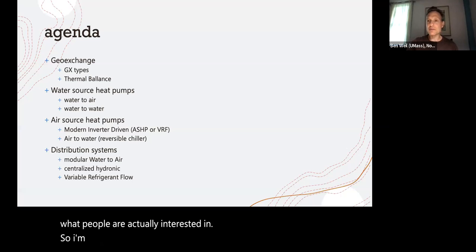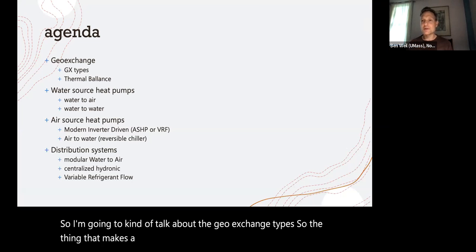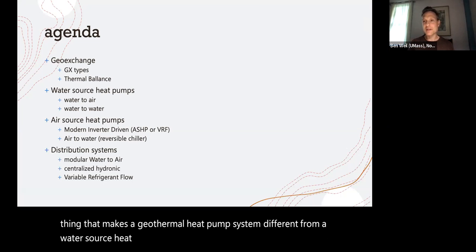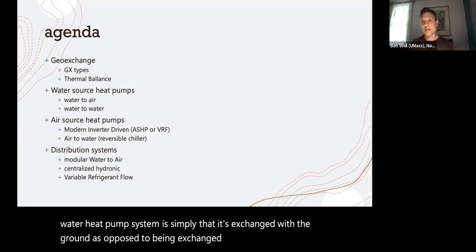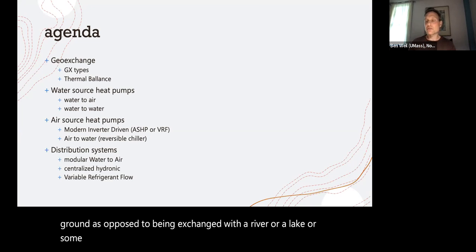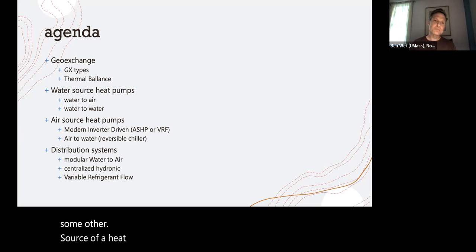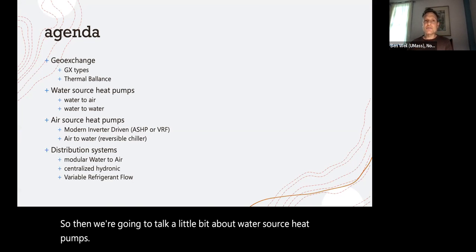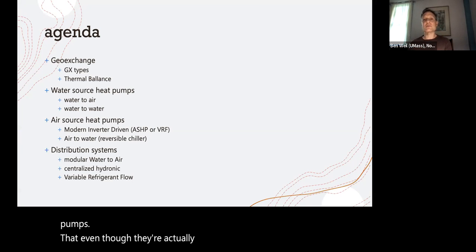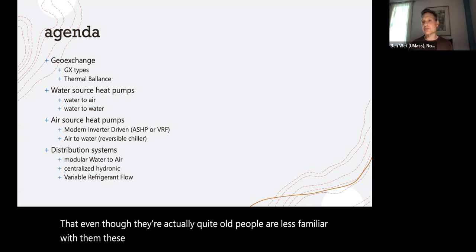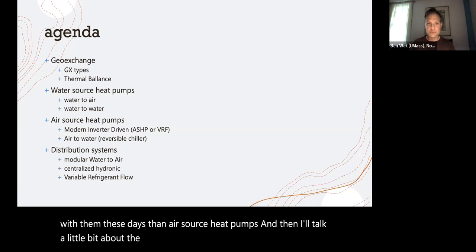So I'm going to talk about the geo-exchange types. The thing that makes a geothermal heat pump system different from a water source heat pump system is simply that it's exchanged with the ground as opposed to being exchanged with a river or a lake or some other source of a heat source or sink. Then we're going to talk a little bit about water source heat pumps that, even though they're actually quite old, people are less familiar with these days than air source heat pumps. And then I'll talk a little bit about the comparison to air source heat pumps.